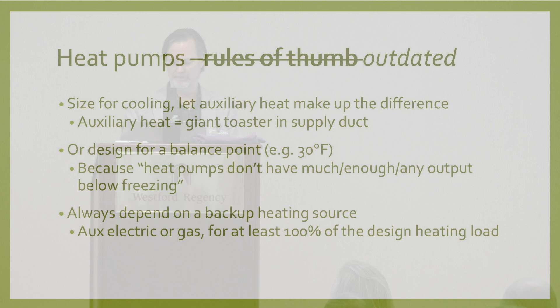But let the auxiliary heat make up the difference between what the heat pump capacity happens to be at the design condition and what the building load is at the design condition. Sometimes people design for an arbitrary balance point because they basically think the heat pump isn't worth using below a certain point.